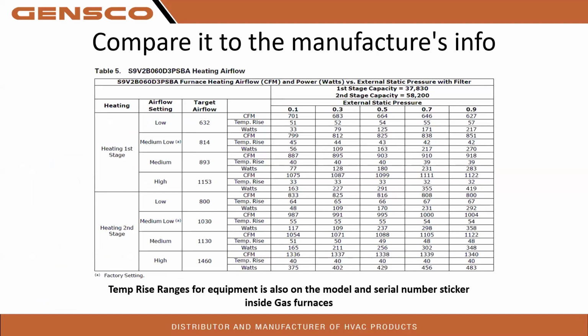Okay, so always compare it to the manufacturer's information, right? So we'll pick on an S9V2 furnace, 60,000. This is a downflow model. We're telling you capacity in first stage, second stage capacity. We're also giving you first stage heating airflow, right? So we're going to have low, medium-low, medium, and high. So depending on how we're set, let's say we're set for medium, we're giving you a temperature rise. Right, we're saying that furnace should have a 40-degree temperature rise at a 0.5 static, and we're also giving you watts of the blower motor, and we're also giving you the CFM generated. So at a 0.5 static on medium, we're moving 903 CFM. We should have a 40-degree temperature rise. So we're giving you all the information.